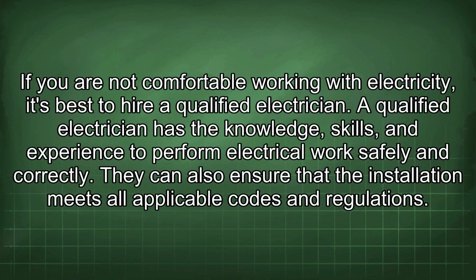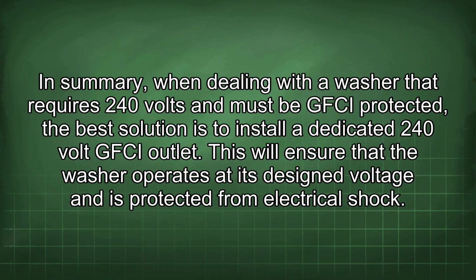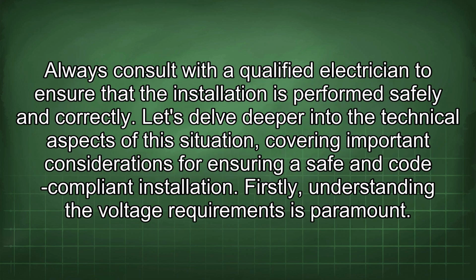They can also ensure that the installation meets all applicable codes and regulations. In summary, when dealing with a washer that requires 240 volts and must be GFCI protected, the best solution is to install a dedicated 240 volt GFCI outlet. This will ensure that the washer operates at its designed voltage and is protected from electrical shock. Always consult with a qualified electrician to ensure that the installation is performed safely and correctly.